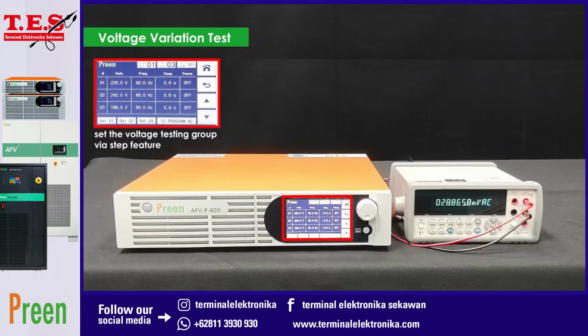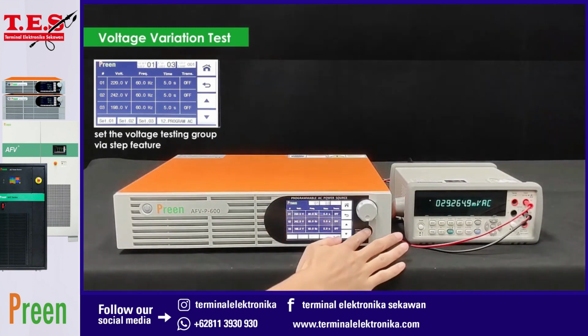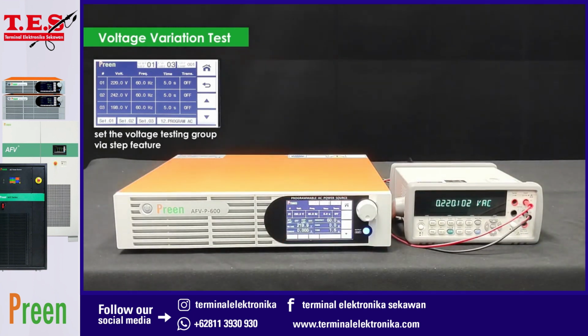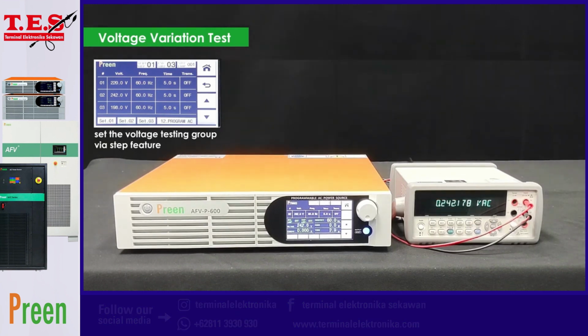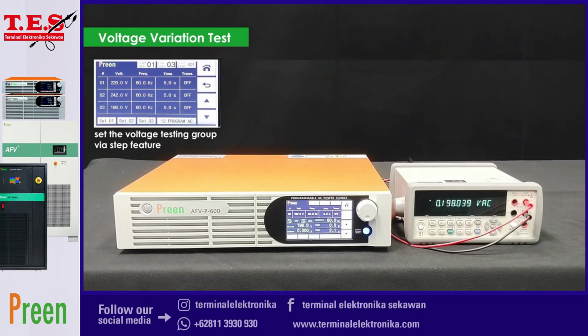Next we will have our programmable AC power source, the AFV-P series for the same application. We set up the voltage testing group via the step feature, which are 220 volt, 242 volt, and 198 volt, same voltage we used for variable transformer. The accuracy of AFV-P's output voltage is up to 0.1% as the meter shows.